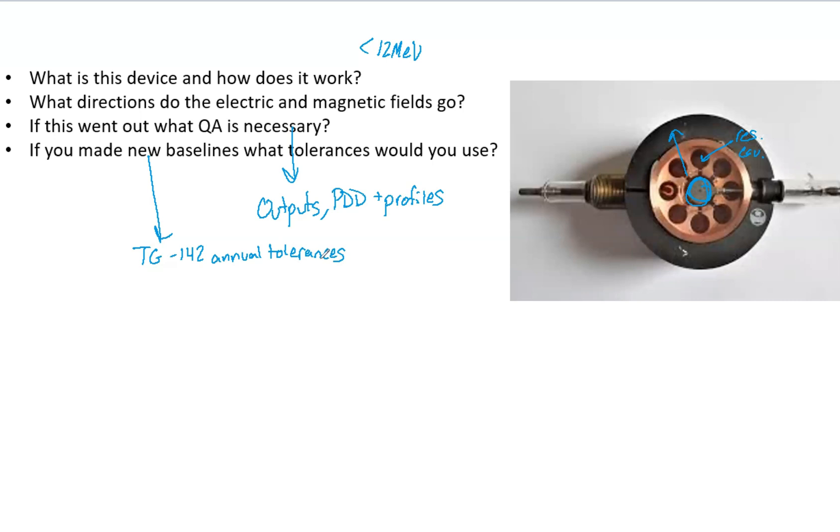The tolerances you want are the tightest tolerances you can get, because you are having to redo all of your outputs and percent depth doses and profiles. You are trying to replicate the original LINAC output and profiles, because those are what is in the treatment planning system.